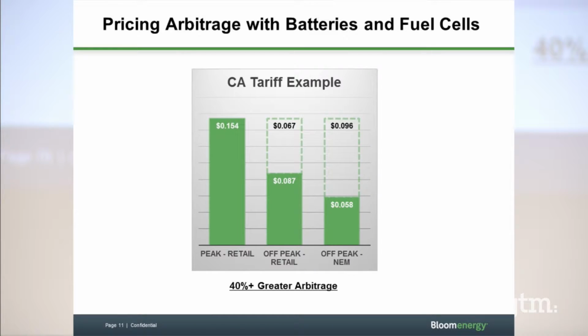If you're doing it with Bloom, typically what we're doing at nighttime is net metering some of the power back to the grid. Now, the issue with fuel cells is that we get wholesale net energy metering, so if we got wholesale reimbursement for that extra power, we'd only be getting about 5.8 cents. But if we take that same 5.8 cent power and instead of pushing it back to the grid, we push it to the batteries, we can now arbitrage it against the 15.4 cents. So we create a far greater arbitrage opportunity, combined with the cost synergies I talked about, to dispatch the storage.